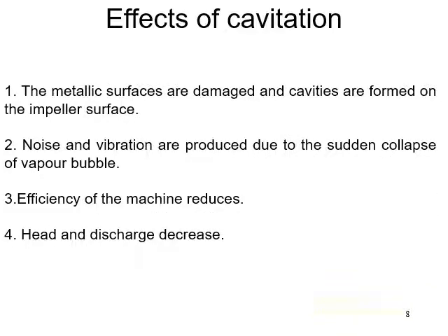Next, what are the effects of cavitation? The metallic surfaces are damaged and cavities are formed on the impeller surface. Noise and vibration are produced due to the sudden collapse of vapor bubbles. Efficiency of the machine reduces, and head and discharge decrease. So these are the effects of cavitation.